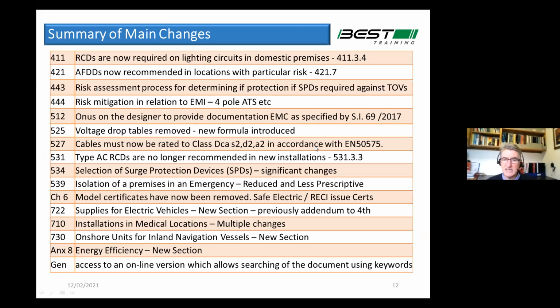A big section here is now that cables must be rated to class Dca-s2,d2,a2. Bit of a mouthful. In a nutshell, it just means PVC cables are no longer acceptable. So the old PVC twin and earths that we use in domestic installations, NYM-J, and all other PVC-based cables cannot be used. So these cables are fundamentally LSZH, so low smoke, zero halogen. A little bit more to that, and we'll touch on that later.